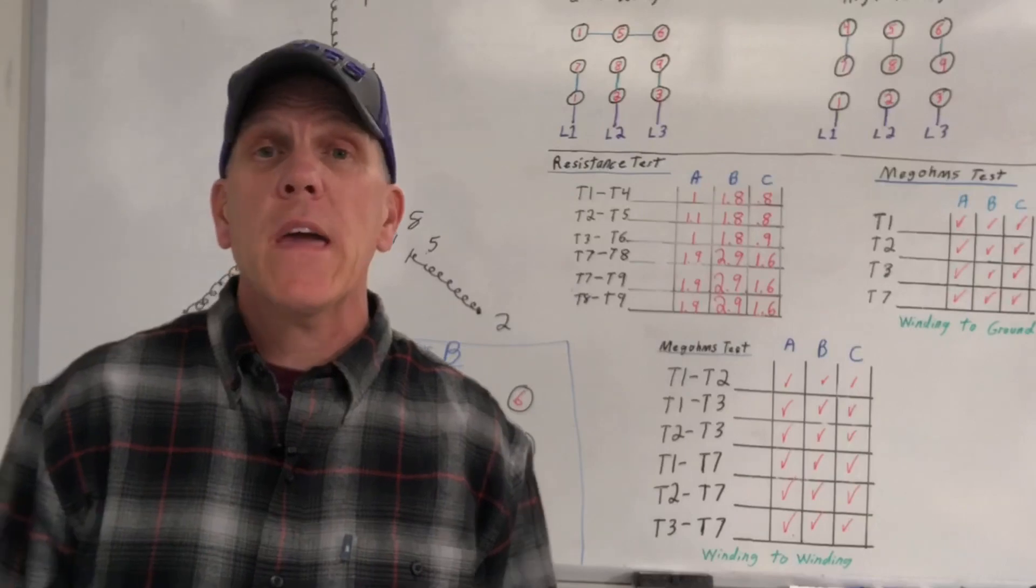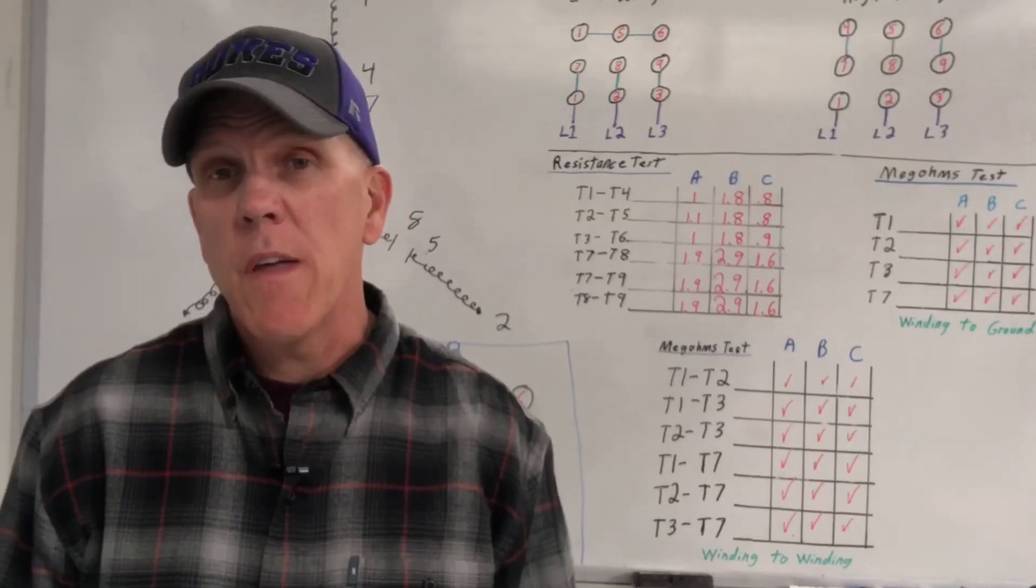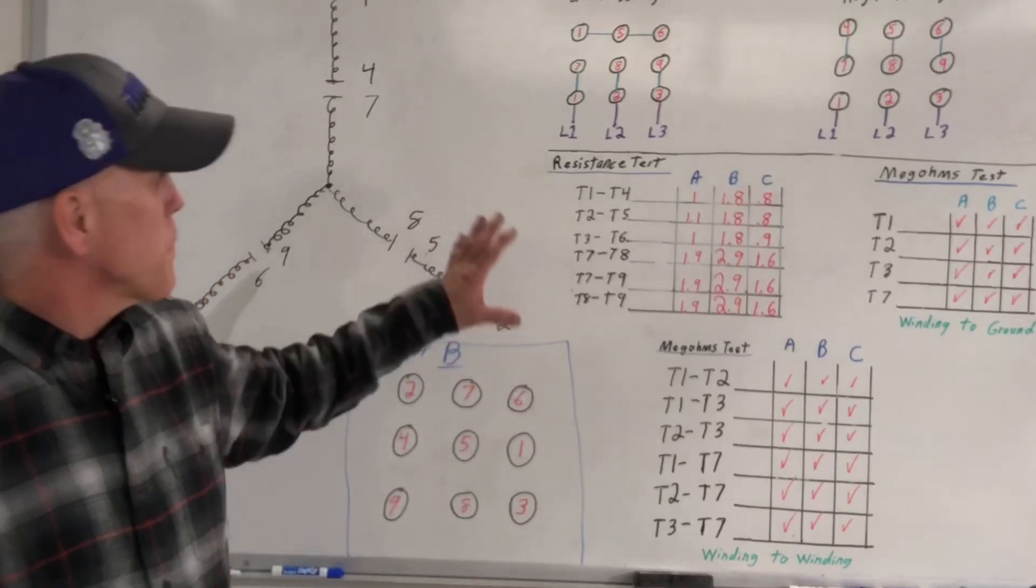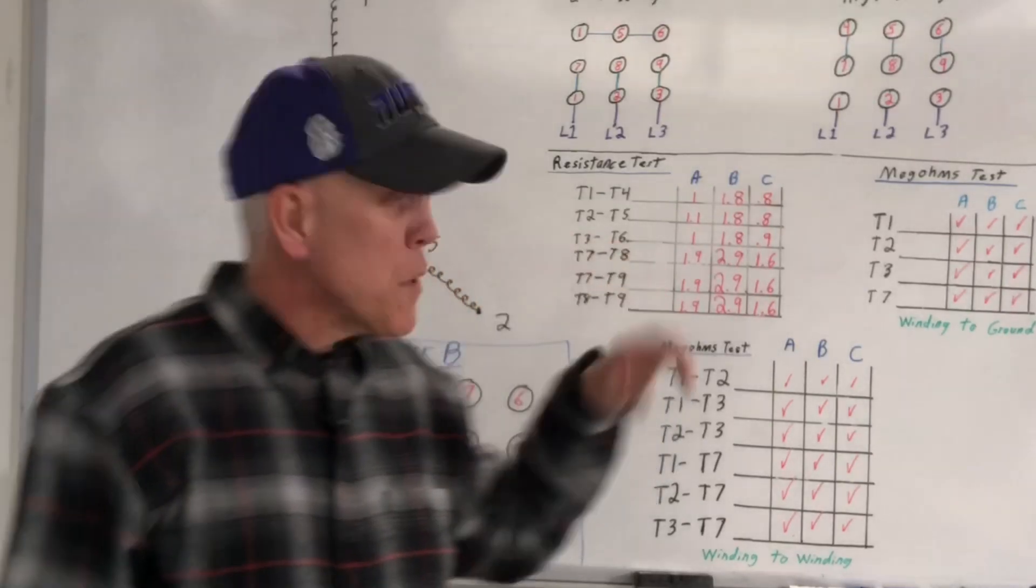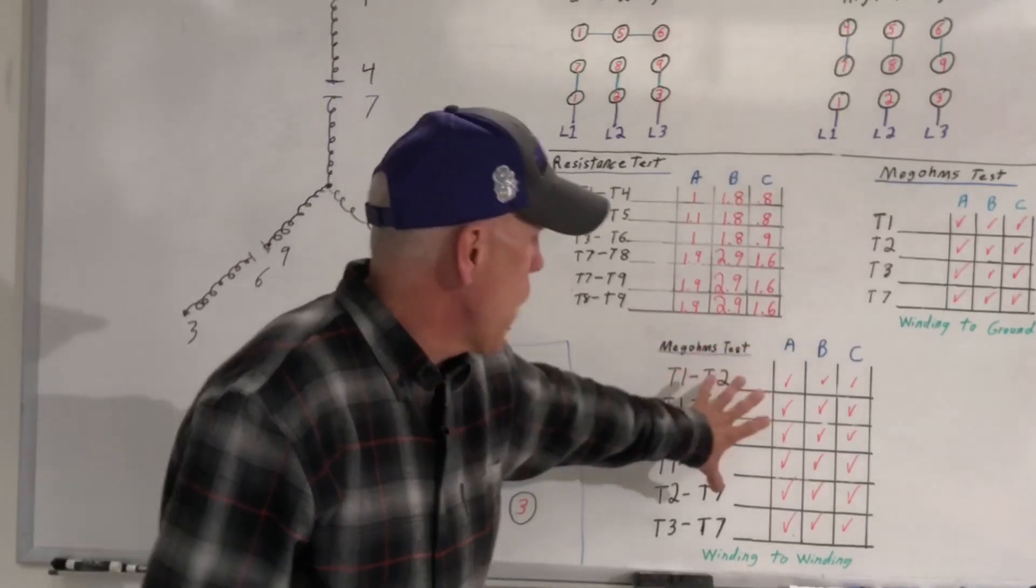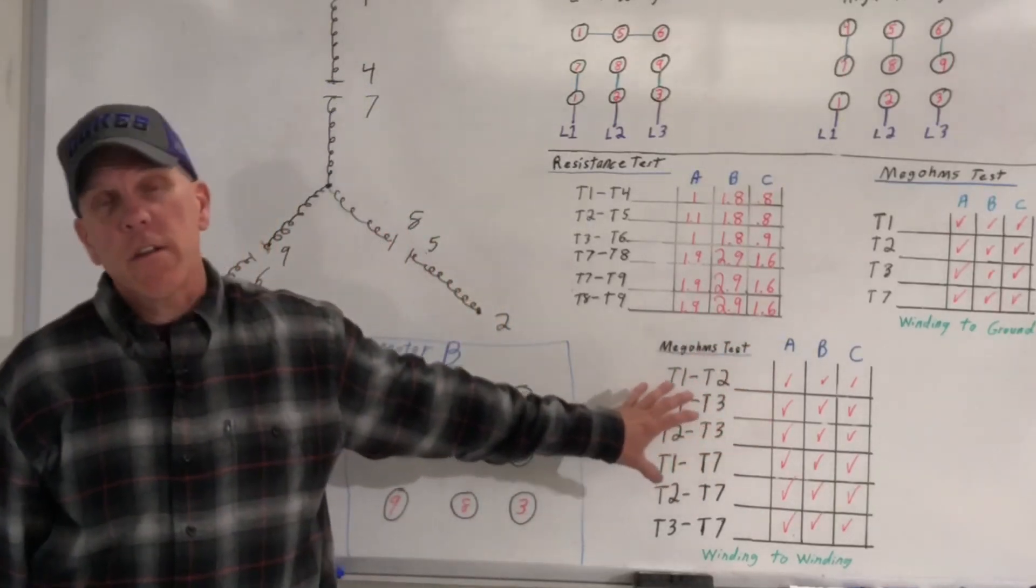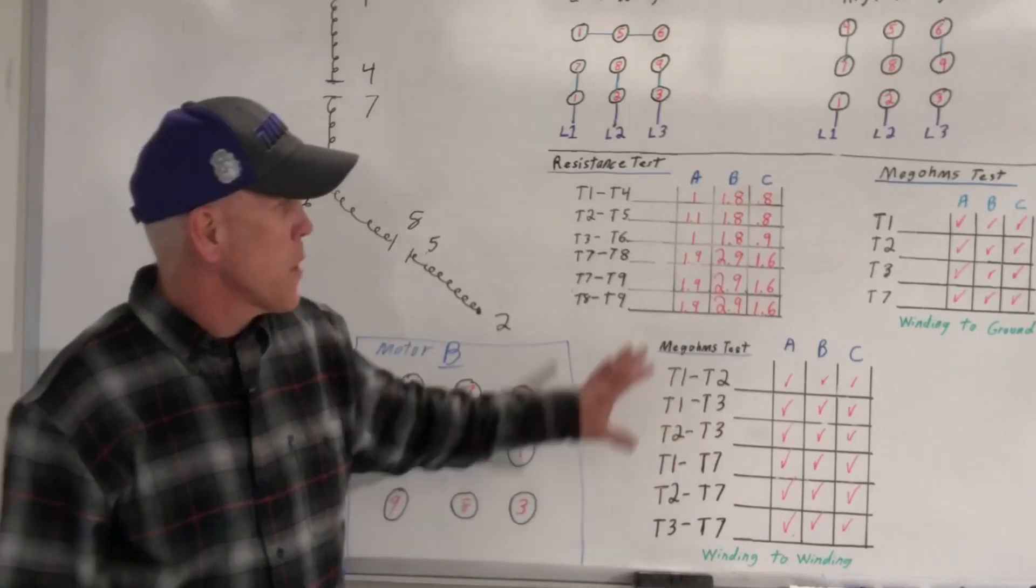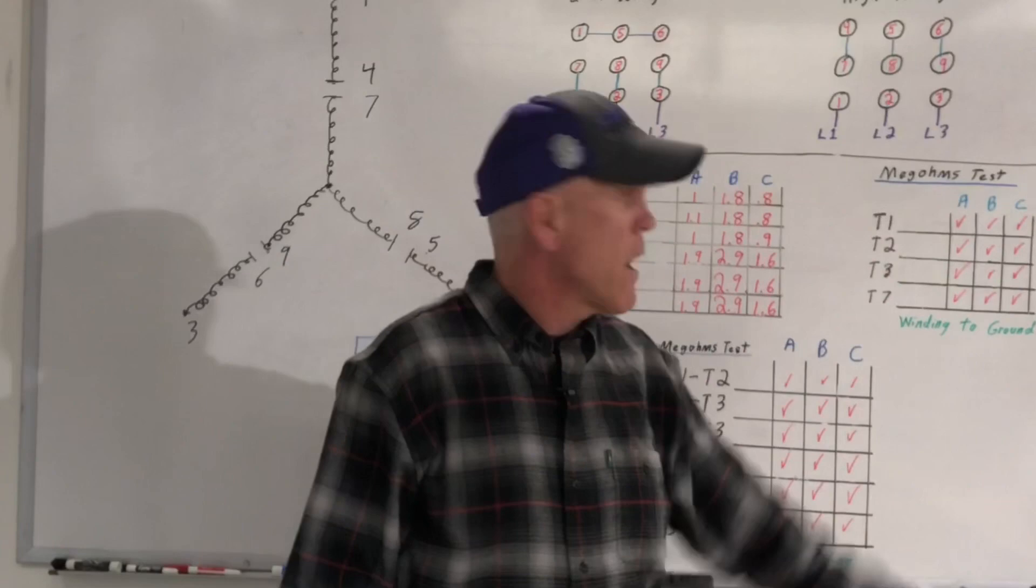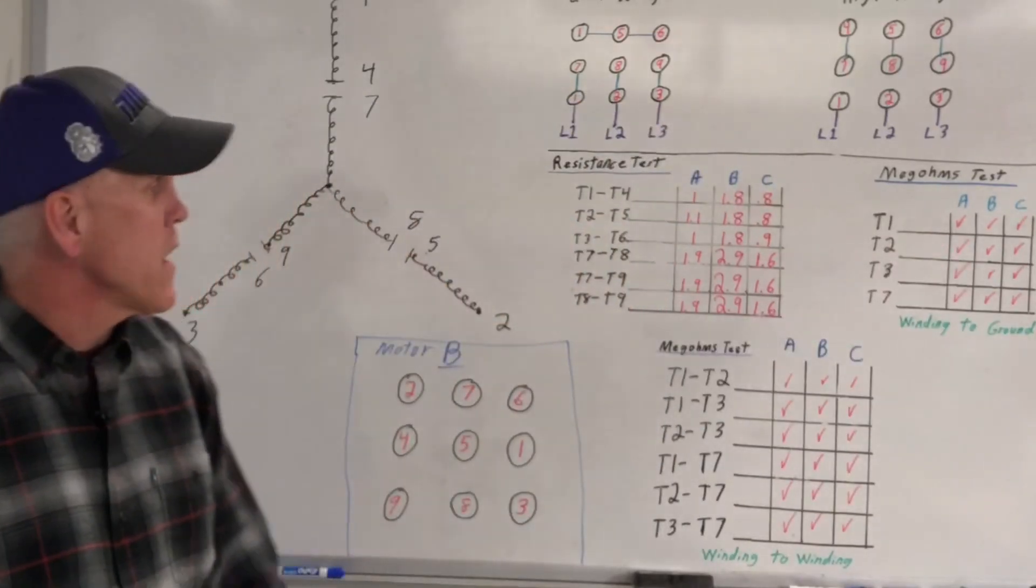Okay guys, I am back and it feels great to be out of that cold wind that was out there. I got all my readings up here. Everything looked pretty good. I've done my mega ohm tests from all my windings. Everything looked good there. Didn't get any readings through my Supco 500. I've done my mega ohm tests for my windings to ground. Everything looked good on there. So I didn't get any readings on that.